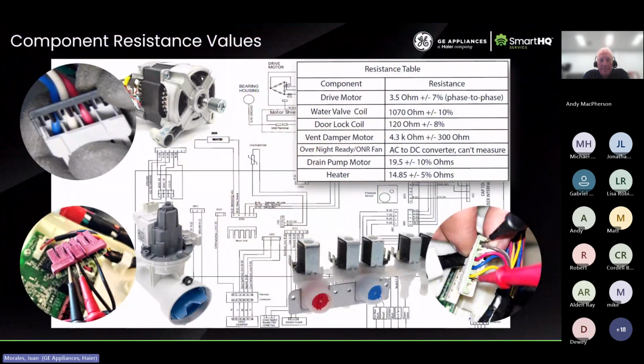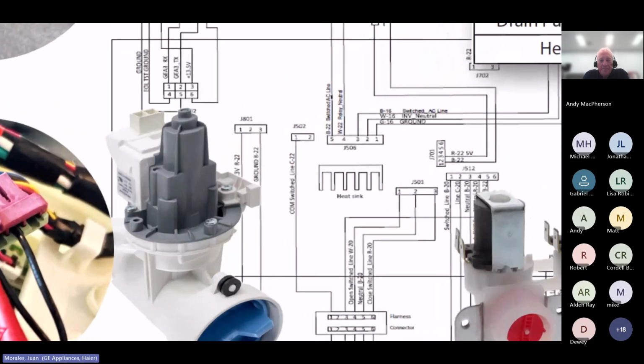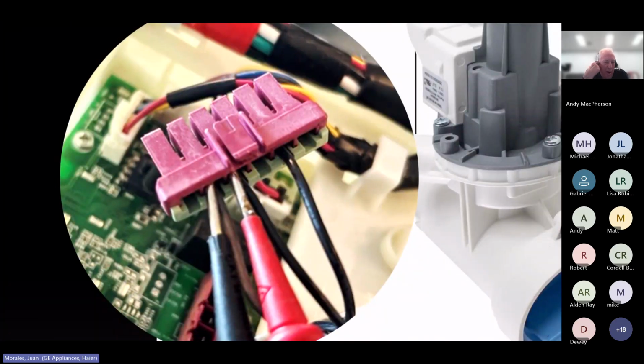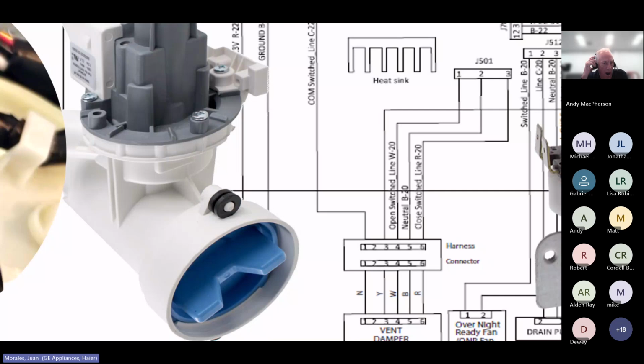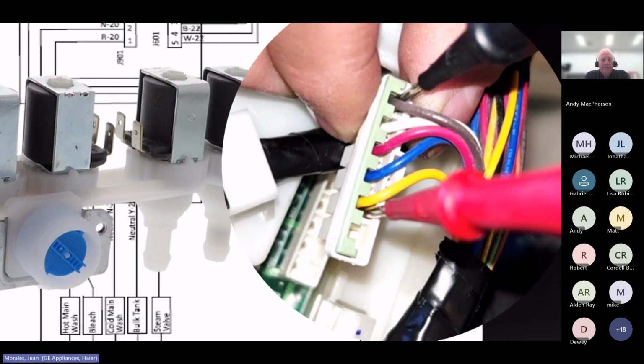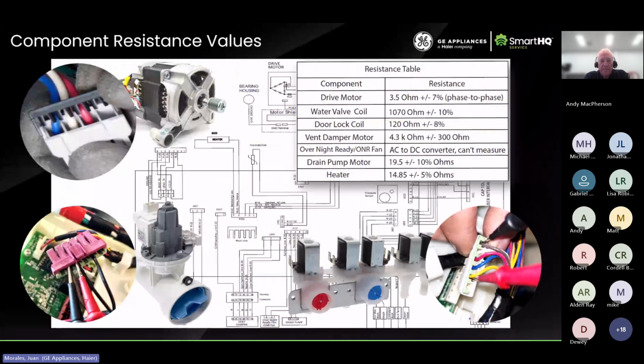The other thing is, and again we're going to go back over here to the slideshow, please make sure that when you measure resistance, you detach the connector. See the drain pump connector? It's detached from the board. See the water valve connector? It's detached from the board. The reason you want to detach it from the board is because if you measure with the connector attached to the board, you're going to be measuring board resistance, and that is going to give you an erroneous value.